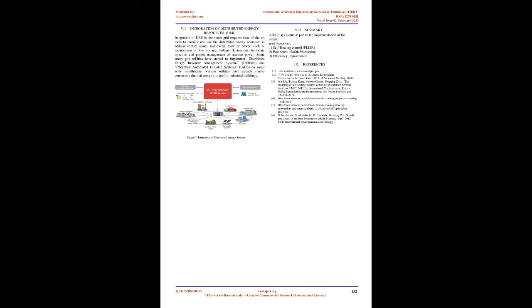SCADA integration typically involves interfaces with a variety of systems and sources of grid information, including GIS for distribution network models, real-time operating and switching information from DMS, measurements and data to DMS and data historians, and measurements and data from MDMS or data warehouses. When interoperable with other systems, i.e., DMS, MDMS, OMS, CIS, GIS, and DERMS, SCADA provides distribution control for substations, feeders, inter-tie points, and distribution equipment, sequencing of events, time-stamped data, trending, and diagnostic data for load management, outage analysis, and demand response.